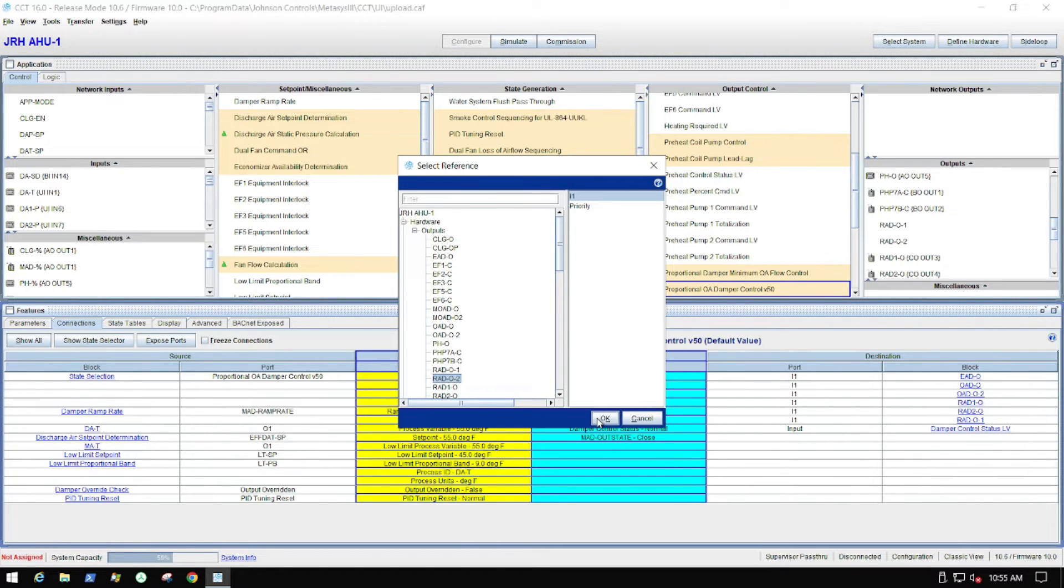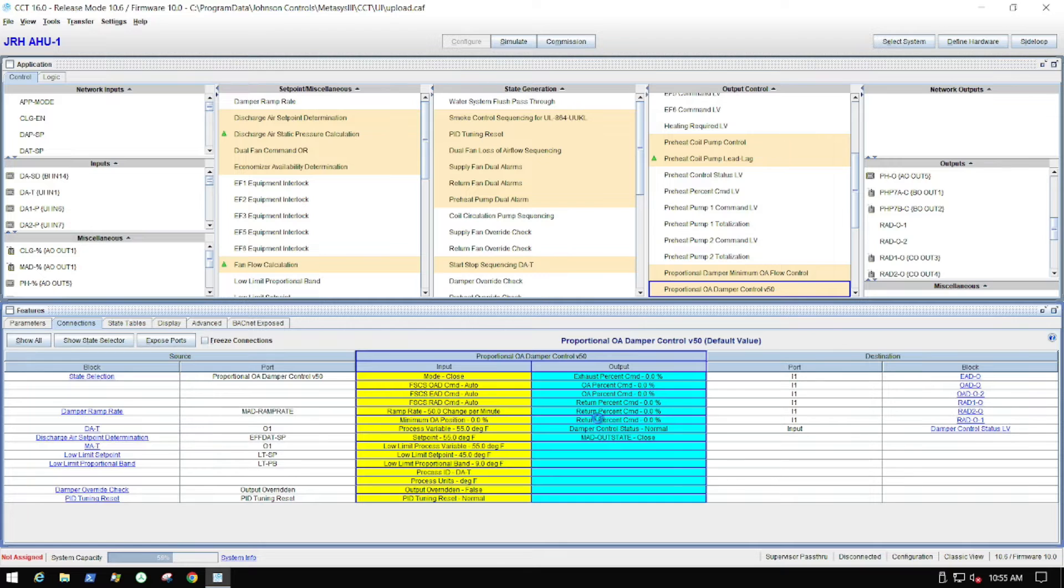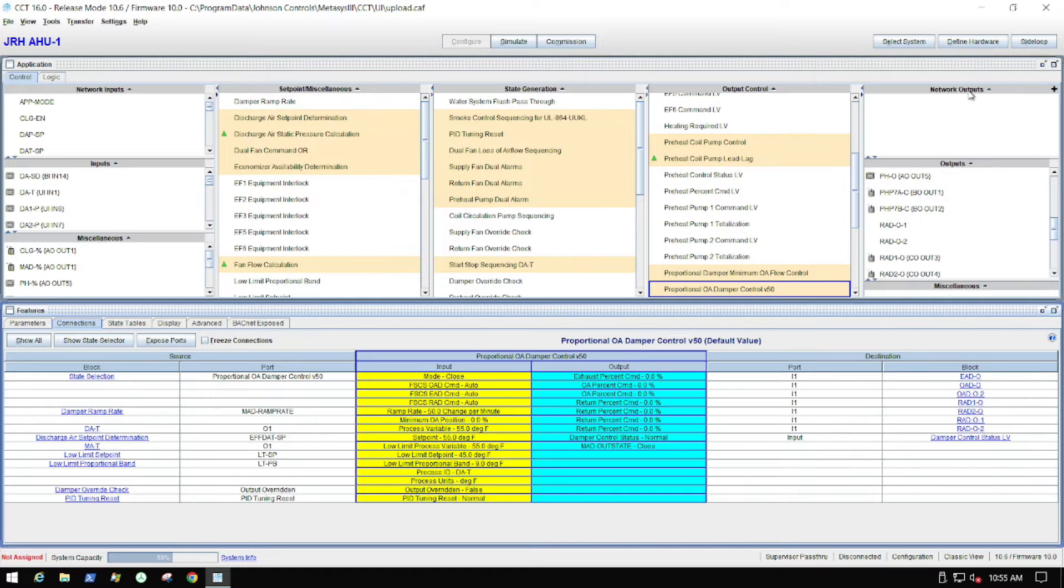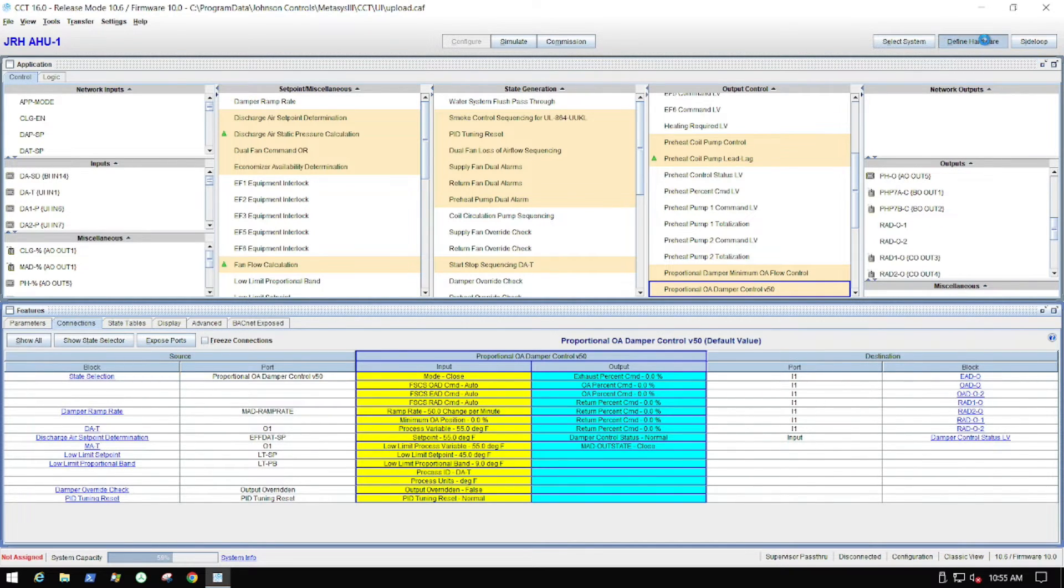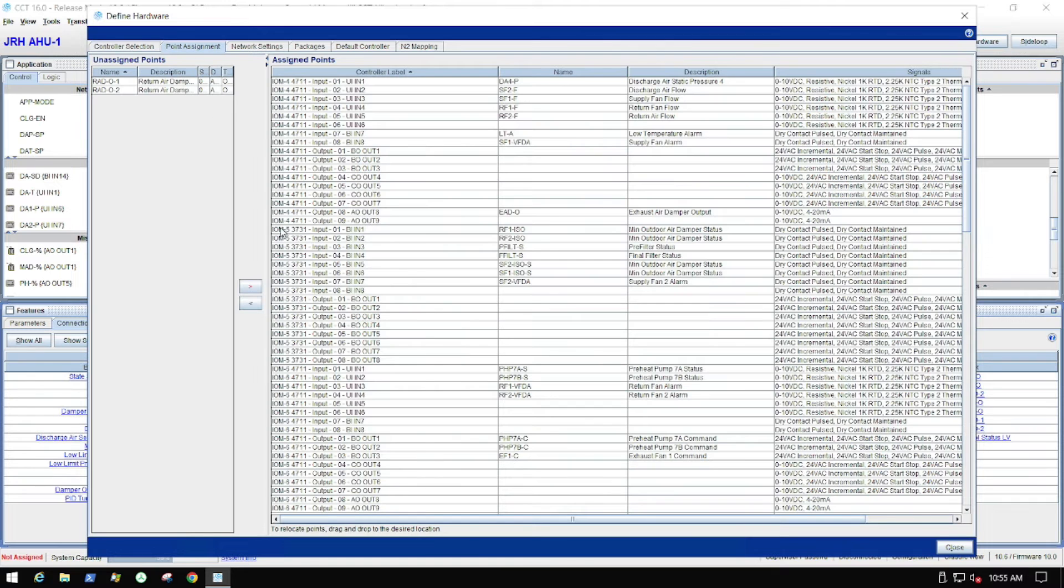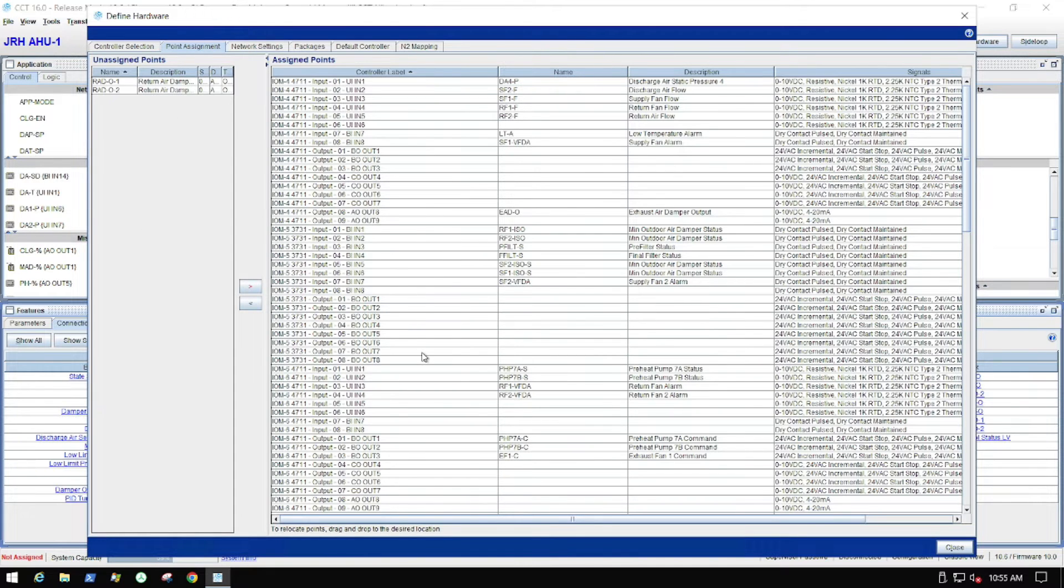The physical modifications that we've done to this machine, it is much easier to run a communication cable and a remote I.O. to drive these new actuators. This is a large project, and this is just one example of it. But now what I have to do is to tie those to a physical output, and I do that under the Define Hardware tab, Point Assignments Options.